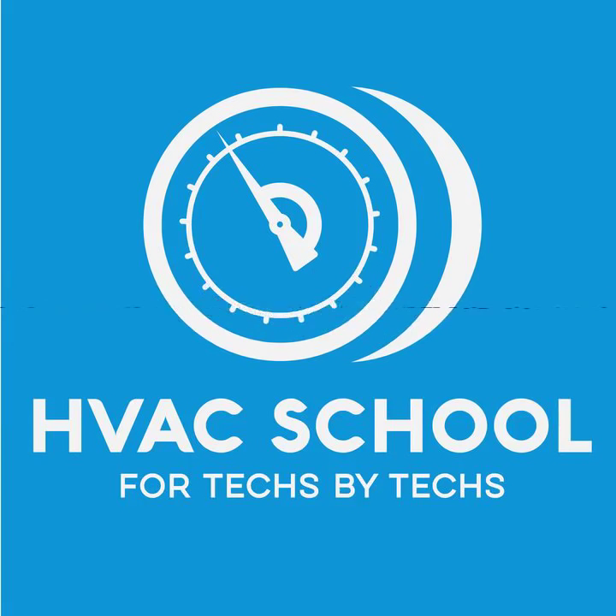So let's say it's a 240 volt appliance, and it's got 20% voltage drop. I'm trying to do math in my head here. I'm stalling. It would be a 48 volt drop in voltage, and so you would have lower voltage than you should to drive the pump potentially. It can cause problems. So you would have to then oversize the wire to make up for the length, but that wire is not going to overheat, because it still would only have 20 amps on it. In fact, adding that additional resistance would actually decrease the total amperage of the circuit, because increased resistance does decrease amperage. But the point at which the resistance exists is where the heat is going to be in that circuit. And so by adding in additional resistance, you are creating voltage drop at that load.